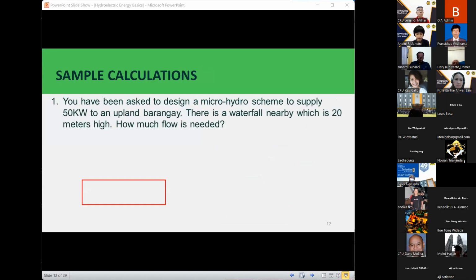Okay, so here's a sample calculation for gross water power. For example, you've been asked to design a microhydro scheme to supply 50 kilowatts to an upland barangay or village. There is a waterfall nearby which is 20 meters high. How much flow is needed? The barangay needs around 50 kilowatts of electric power for their needs.